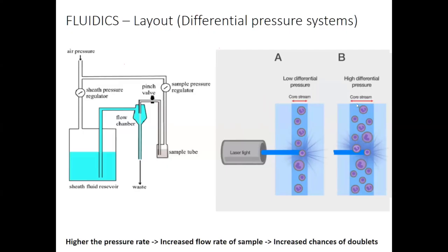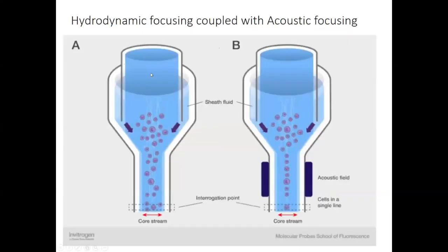Cells, more amount of sample will be dispensed into the flow chamber. And since the sample is already hypercellular, you cannot achieve a single file pattern, though you have efficient sheath fluid flowing by the sides, right? So hydrodynamic focusing is lost and the data will be bad. Clear?